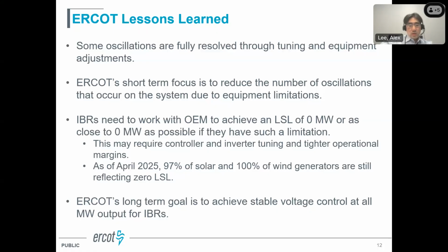IBRs need to work with OEMs to achieve LSL at 0 megawatt or as close to 0 megawatt as possible if they have such limitations. Even if we allow them to not provide reactive response at 0 megawatt output, a lot of newer interconnected resources tend to have a learning curve where they'll have to work closely with OEMs to minimize their LSL, so they have a wider range of megawatt output where they can provide reactive capabilities. This requires controller and inverter tuning and tighter operational margins.